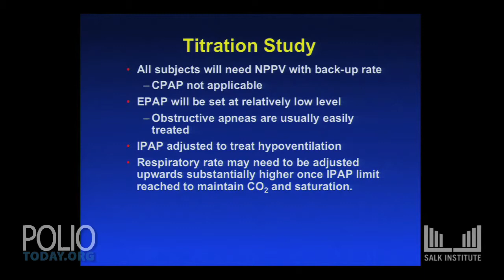What we do is we set the EPAP, the expiratory pressure, to a relatively low level because obstructive apneas are usually pretty easily treated, and we use the IPAP to treat hypoventilation, and then lastly, the respiratory rate, we dial it up. So this is what we tell the technicians to do. Start the EPAP at 4 to 5, start the IPAP at around 8 centimeters of water, slowly increase it to treat the hypoventilation, and then later bump the respiratory rate up.